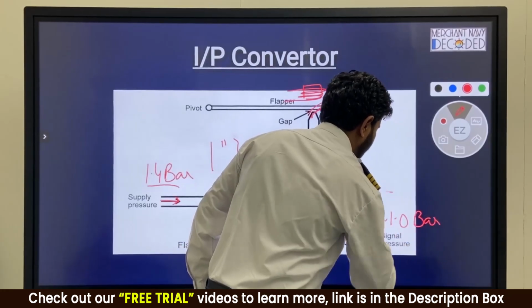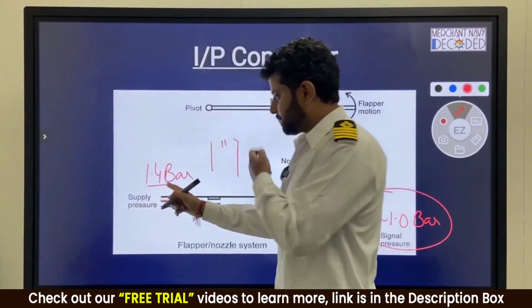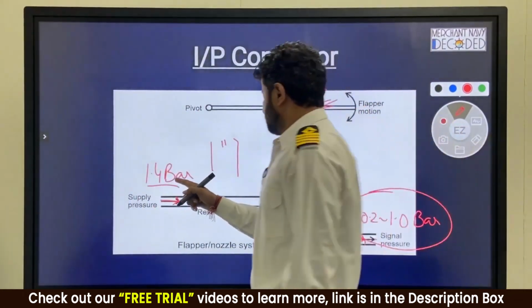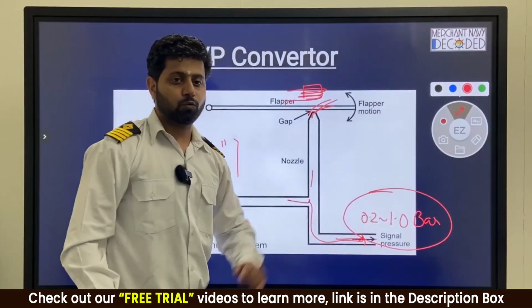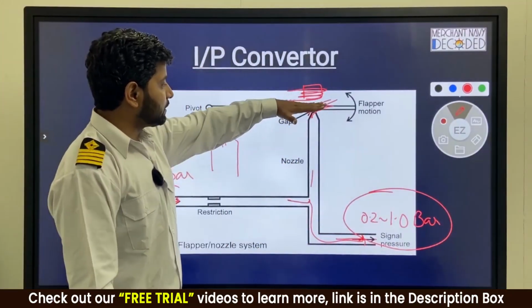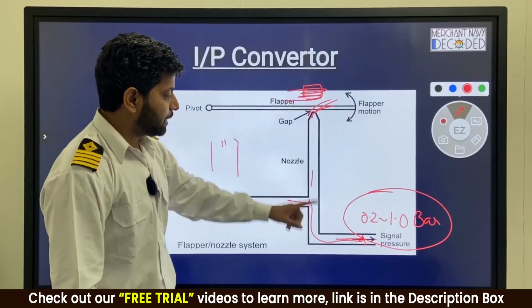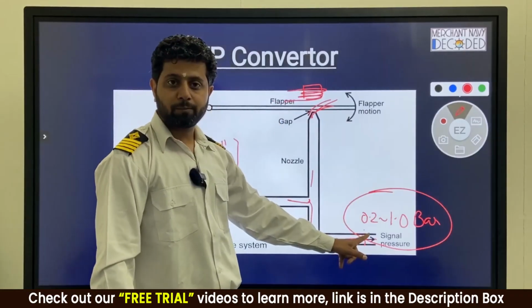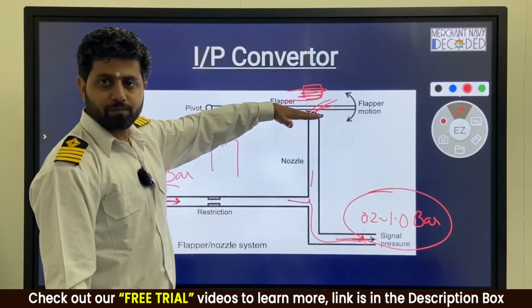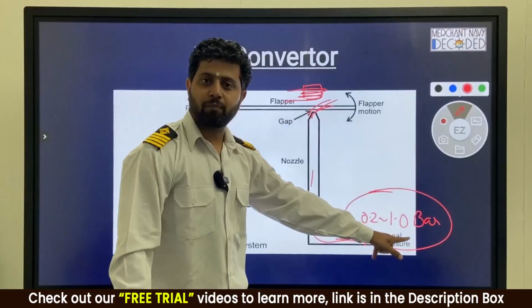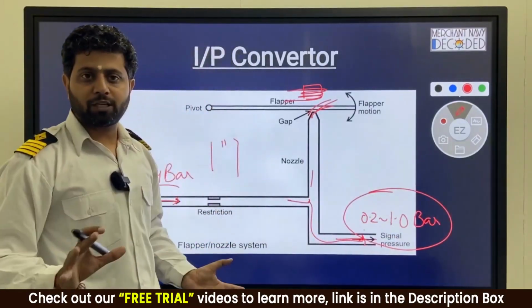Remember this. The input supply pressure of air is 1.4 bar, but the output which is coming is 0.2 to 1 bar. So in case this flapper nozzle is maximum up, then the minimum air coming from here is 0.2 bar. And when it is maximum down, then the maximum air coming is 1 bar. So this is how this flapper nozzle arrangement works.